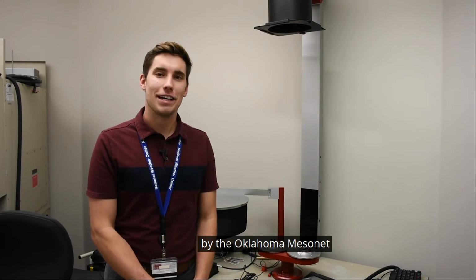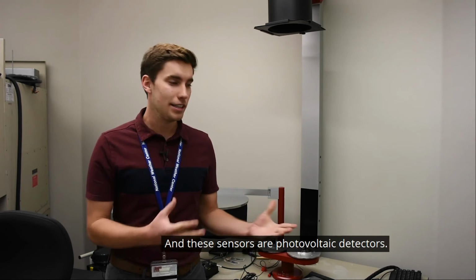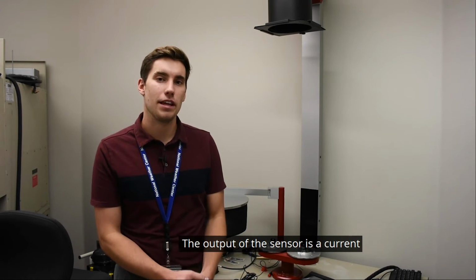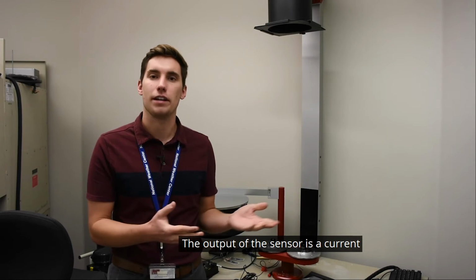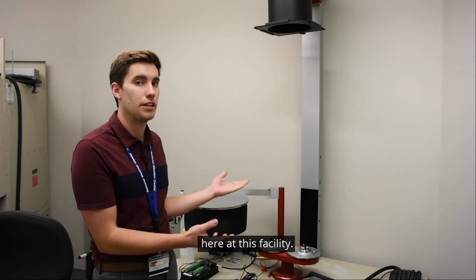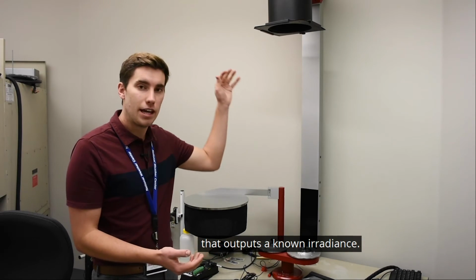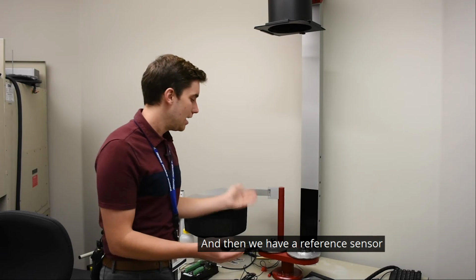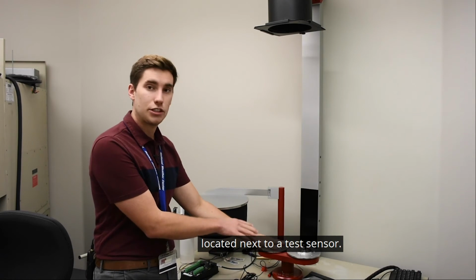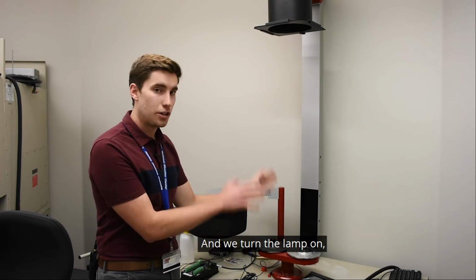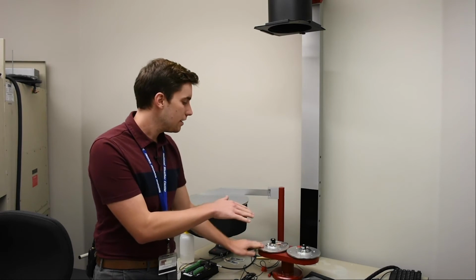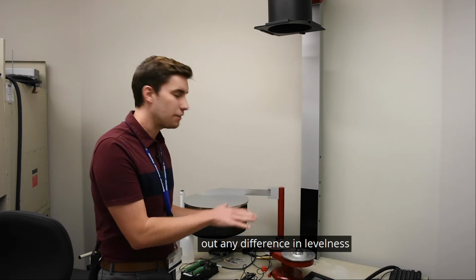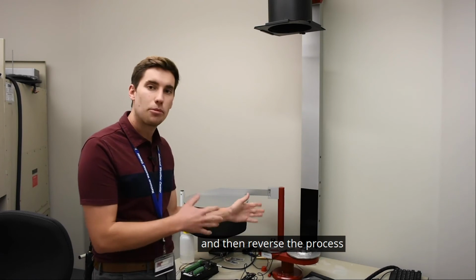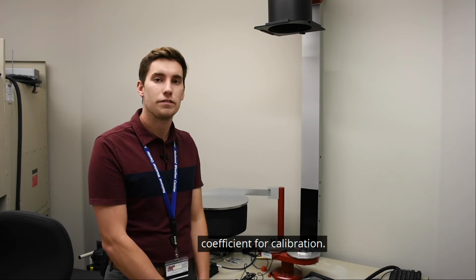Another variable measured by the Oklahoma Mesonet is incoming solar radiation. And these sensors are photovoltaic detectors. The output of the sensor is a current which is proportional to the solar radiation. We calibrate them indoors here at this facility. We have a lamp mounted above that outputs a known irradiance. And then we have a reference sensor located next to a test sensor. And we turn the lamp on, take a measurement, swap the sides to average out any difference in levelness, and then reverse the process to make sure we get a stable coefficient for calibration.